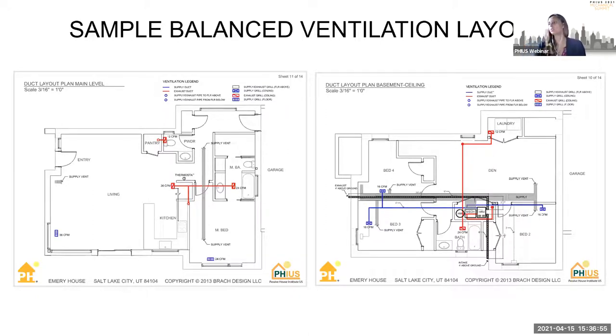Okay. So control scenarios, I'm thinking you're talking about demand controlled ventilation. So yes, there is an option to have demand controlled ventilation. It's a little bit more challenging in terms of commissioning. But there is the option, yes, if you can prove and commission that the system will run up to a certain rate based on CO2 or particulate matter in the space. There's a couple of units that have been in certified projects that can achieve that.